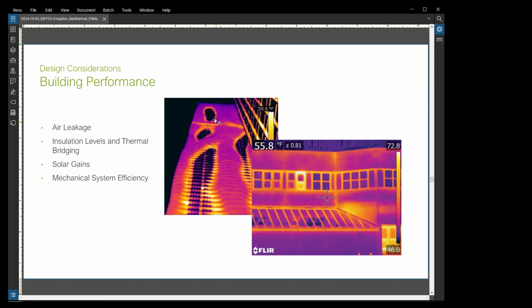So what we did was we employed a geothermal monitoring firm. Their sole job is they've got temperature sensors on the inlet and the outlet of the well, as well as monitoring pump speeds, water rates, flow rates, and volumes. They're just paying attention on an annual basis to see what's going on.